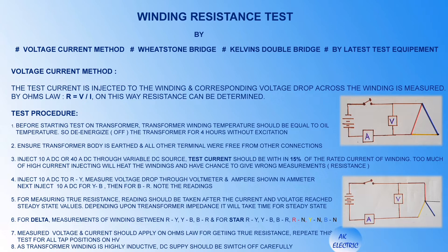Test procedure: before starting the test on a transformer, the transformer winding temperature should be equal to oil temperature. So de-energize the transformer for four hours without excitation. Ensure the transformer body is earthed and all other terminals are free from other connections. Inject 10A DC or 40A DC through a variable DC source. Test current should be within 15% of rated current of the winding. Too much high current will heat the windings and may give wrong measurements.